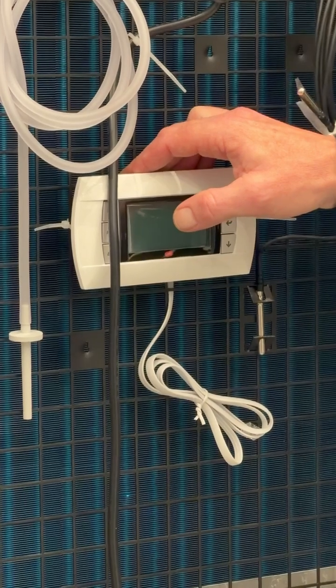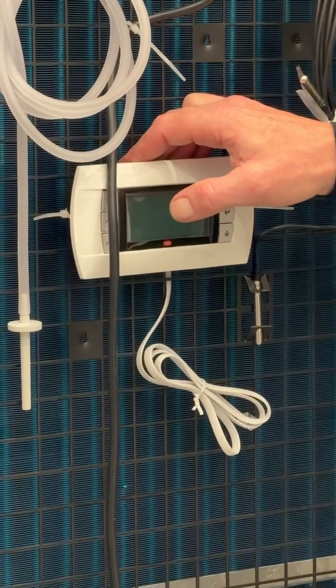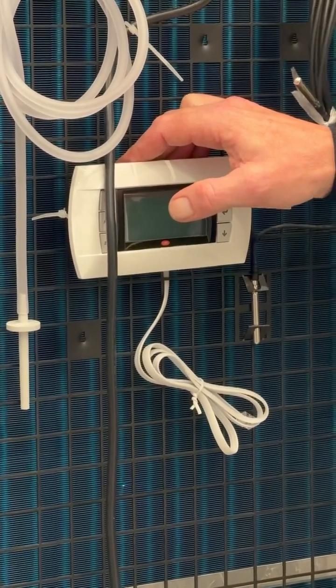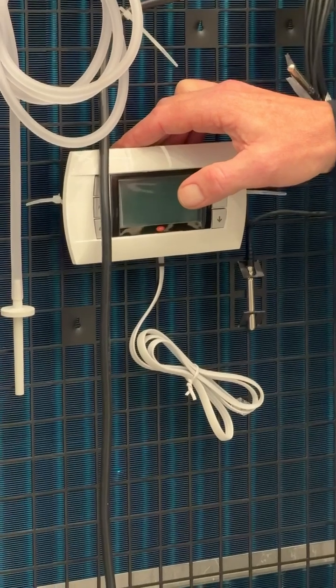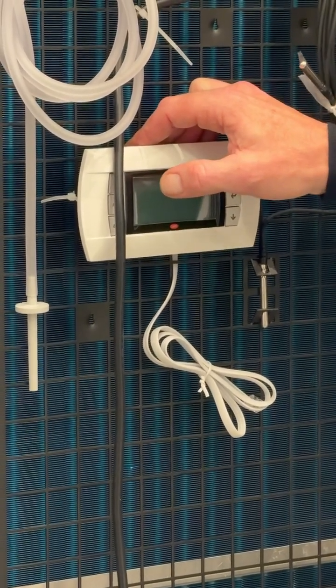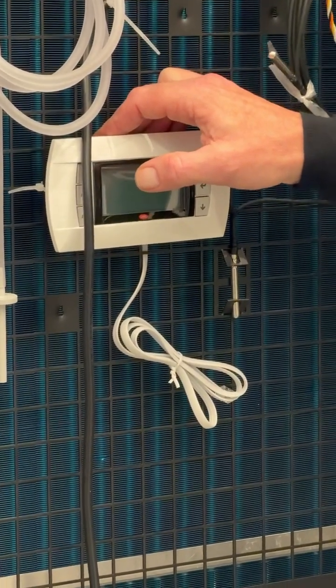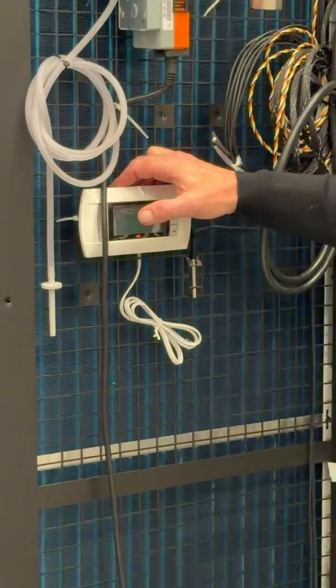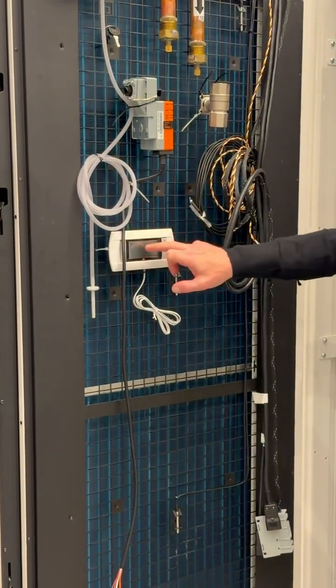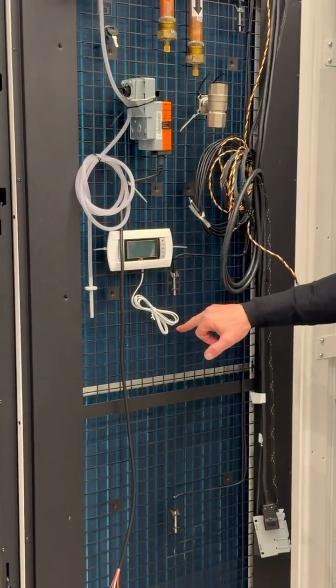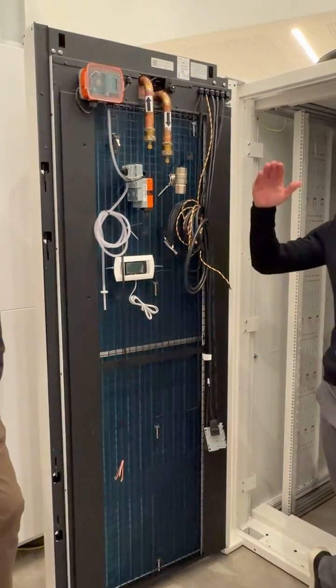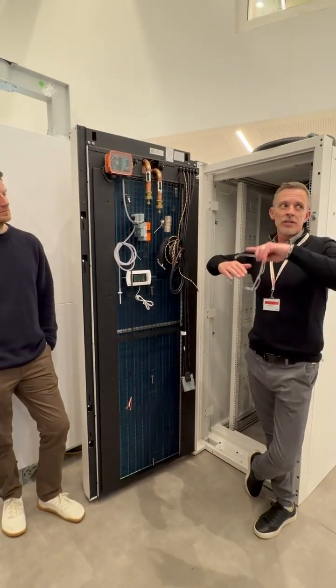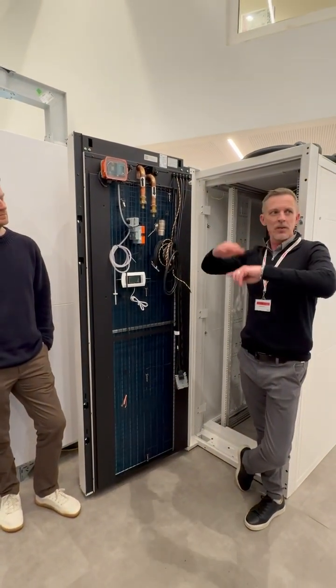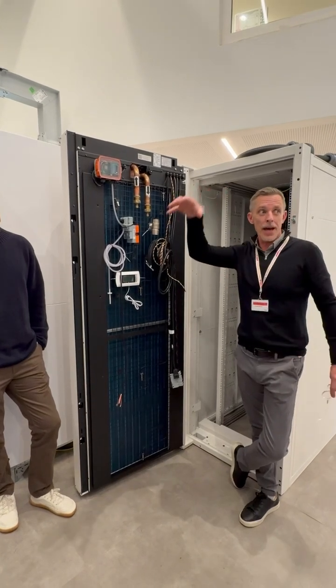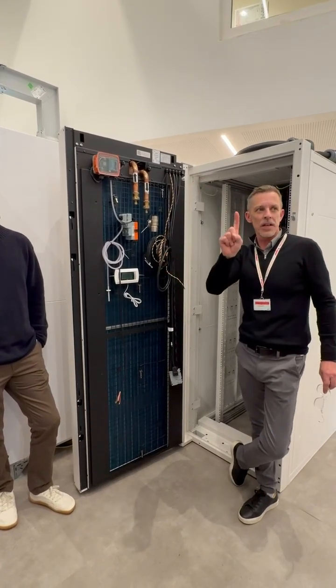Remember what I said in there when we talked about connecting to existing infrastructure. If the existing infrastructure is 18 degrees in, 26 out, ambient temperature of 24, we'll commission this door to run at that. And what that will mean is that door, with any variance in temperature, increases the fan speed from 10%, 20% to 100% to bring the ambient temperature down to the set demand.